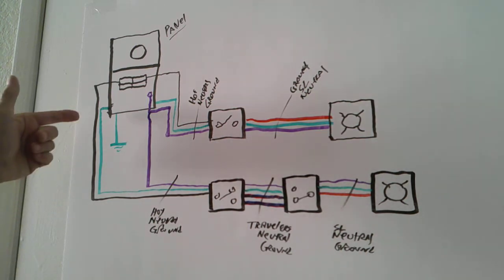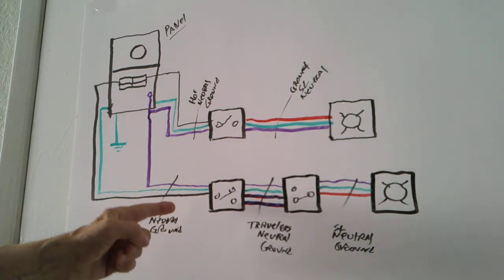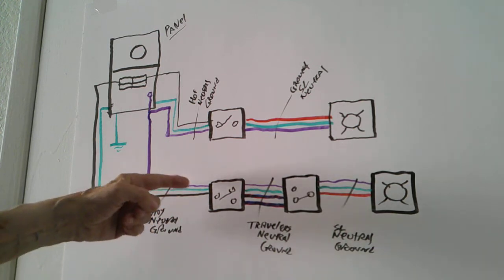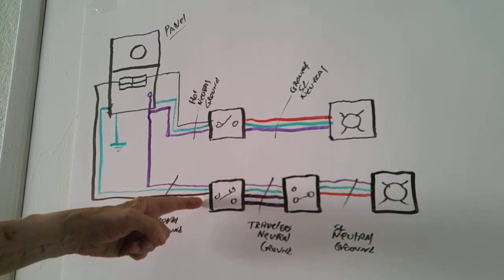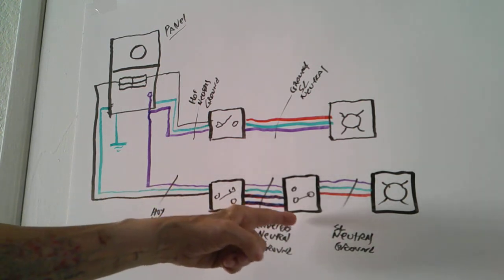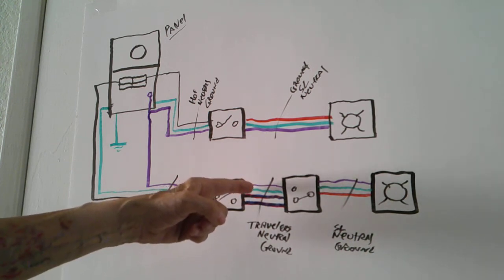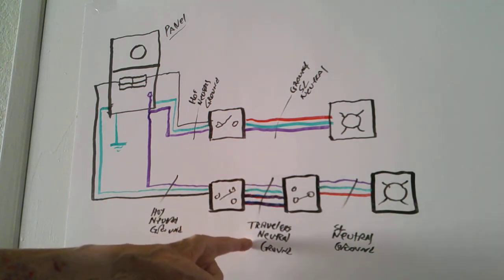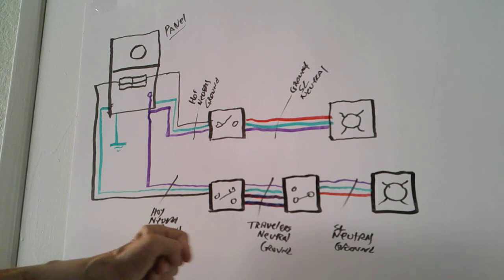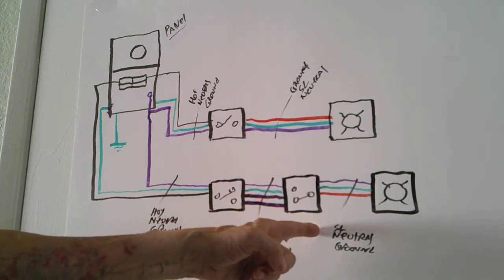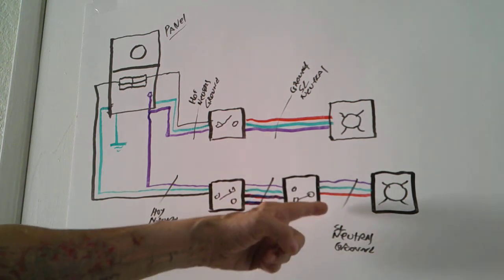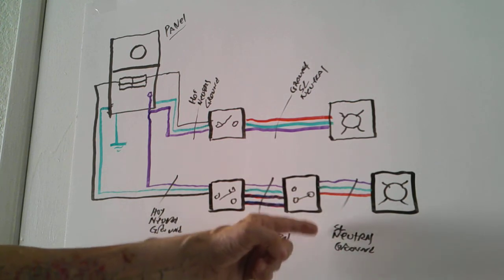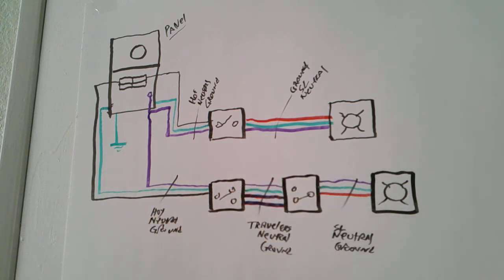Now on our second circuit we have a hot wire, a neutral, and a ground coming into this three-way switch. And going from three-way switch to three-way switch we have a ground, a neutral, and two travelers. And then our final circuit that's going from the three-way switch to the light will have a neutral, ground, and a switch leg. Okay, so that designates what this drawing is all about.